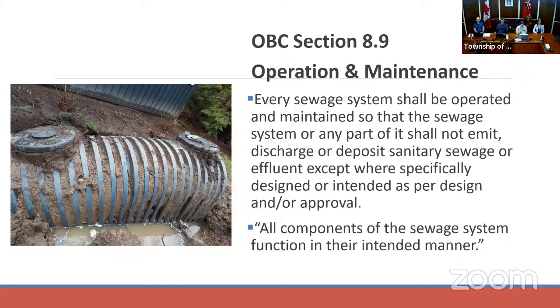Maintaining healthy grass cover and removing deep rooting plants can go a long way to preventing system failure and saving you large expenses. Fast-growing plants such as raspberry bushes or invasive Japanese knotweed can quickly spread roots into distribution piping, causing a system to plug and fail. Similarly, water-loving trees with expansive root systems such as silver maple and willows can quickly destroy a leaching bed.